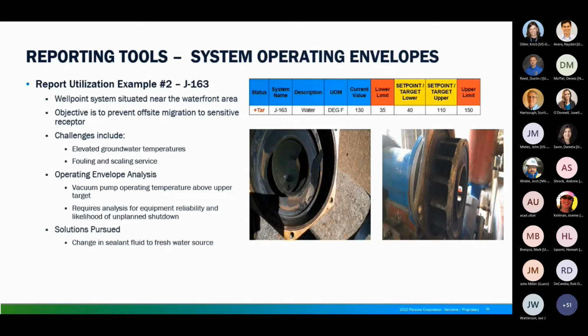We also used the feedback from here to pursue a solution site-wide that we're currently in the process of executing, which is to change that seal fluid to a fresh water source and move away from using recovered groundwater. Because as you can see from the cutaway pictures of one of the planned outages we took, when we started to see that temperature creeping up, you can see a lot of the black scaling present in the vacuum pump housing, as well as the vanes there.